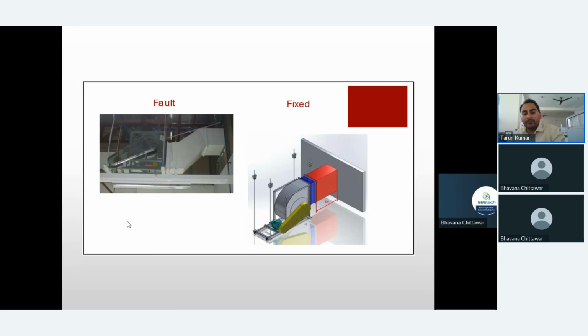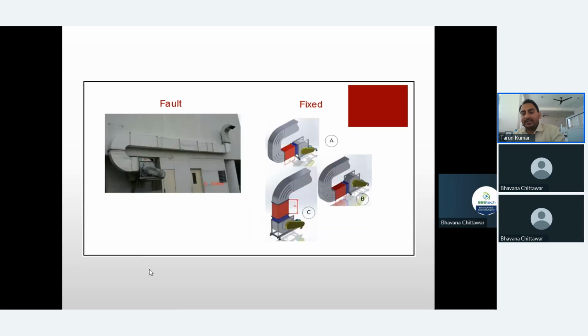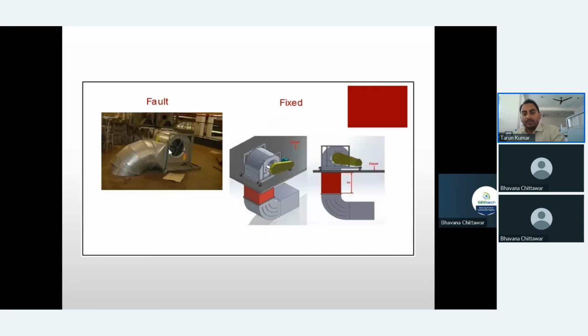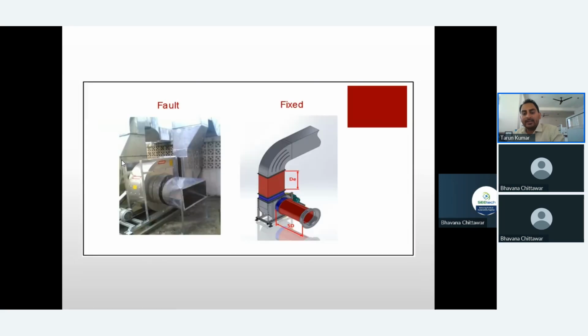So we have to always be careful that we should minimize the bends, and any kind of immediate bend. For such arrangements, we can think about what the best fan orientation would be, to make our system better than the existing one. You can see here also it can be taken with the top discharge, and these 1, 2, 3 bends are immediately avoided, and your pressure loss is reduced drastically. In a further photograph, you can see the down blast kind of arrangement, where one bend is avoided immediately.